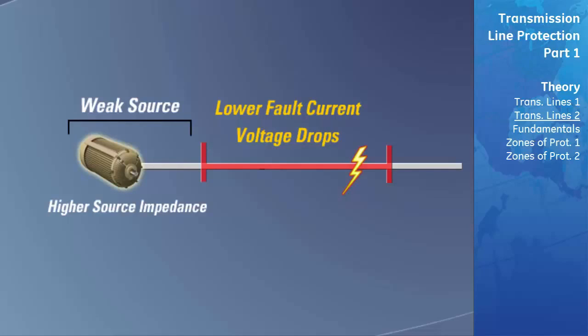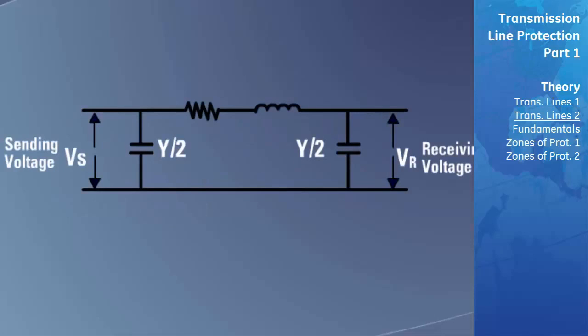At the time of a fault, the system impedance ratio must be considered when determining the type of protection needed and the speed at which faults need to be cleared by relaying. When the current or voltage levels need to be accurately calculated at a specific point on the line, the protection engineer needs to draw an equivalent model of the transmission line. Different models are used for different lengths of line, and these models are in three categories: short, medium, and long lines.